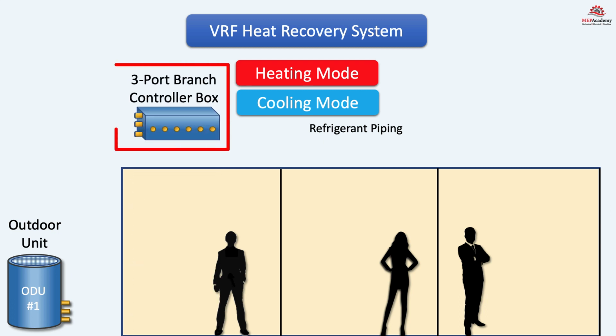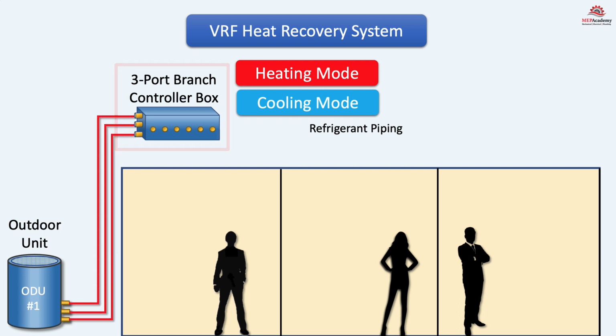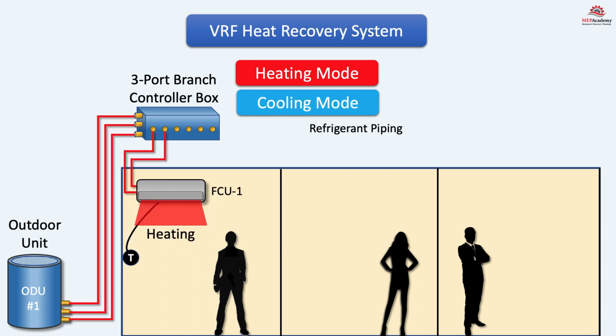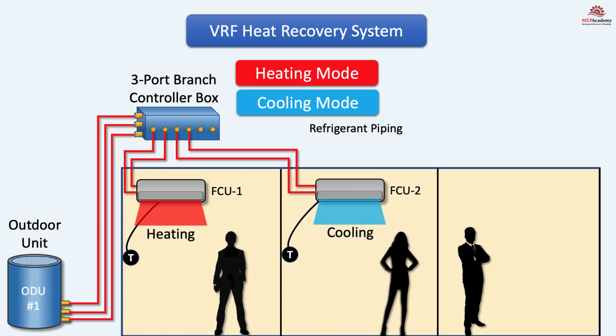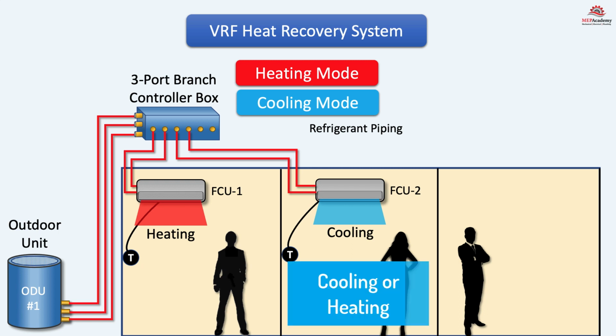if we install a 3-port branch controller box and connect the refrigerant piping to the outdoor unit, we can then connect fan coil number 1 to the branch controller, allowing that office to choose to be in heating or cooling mode, in this case heating. Then, without having to install another outdoor unit, we can add fan coil number 2 to the branch controller, and that office can be in cooling mode.